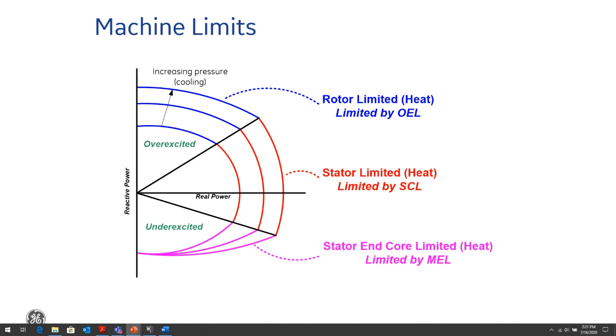System problems such as load rejection or islanding can also cause this. When we suddenly lose loading, the machine cannot correct instantaneously, so it goes into an overspeed condition and then into an overexcited condition. The overexcited condition not only affects the generator, but it affects transformers too, because, as with the generator, the core becomes saturated and that causes overheating. Flux starts to flow where it's not meant to flow and causes overheating and eventually damage.